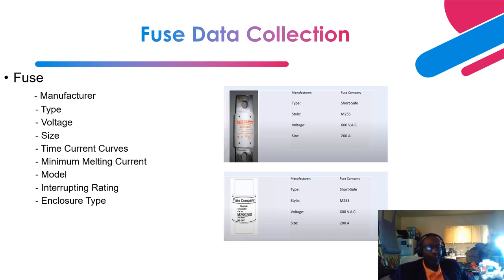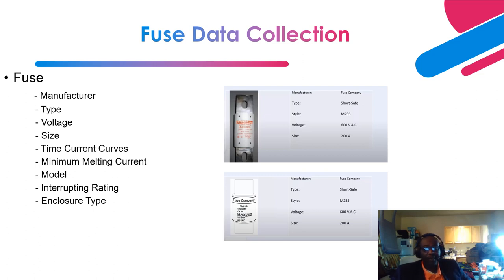Next is data on fuses. For a fuse, you need the manufacturer, type, voltage, size, TCC curves, minimum melting current, model, interrupting rating (symmetrical), and enclosure type — where the fuse is located. On the right-hand side is a typical fuse example showing the manufacturer, type, style, voltage, and size — an example of what you are collecting.